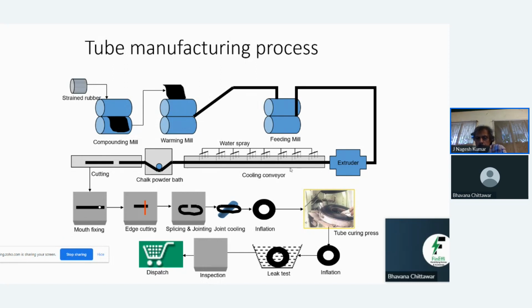So now here, the width of this tube is only 3 inches, but the spray is almost 1 foot. So where the tube is not there, water sprays are happening. So you cut off some of these nozzles and restrict to only 3 inches. So about 60% of the flow can be controlled, reduced. So here there was a case where we replaced the 10 HP by a smaller pump, and one pump which directly sends it to the cooling tower, another pump which sends it to the nozzle.